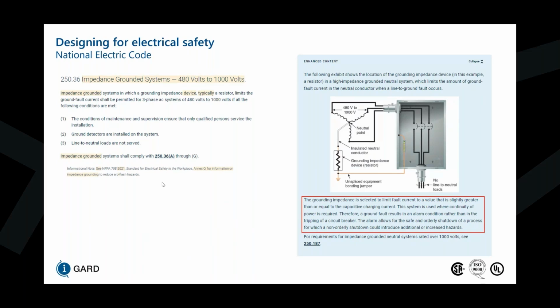In addition to that, we noticed that the National Electric Code doesn't have a requirement to provide resistor monitoring. It's only about ground fault detection in this case. Now, the grounding impedance is selected to limit fault current to a value that is slightly greater than or equal to the capacitive charging current.